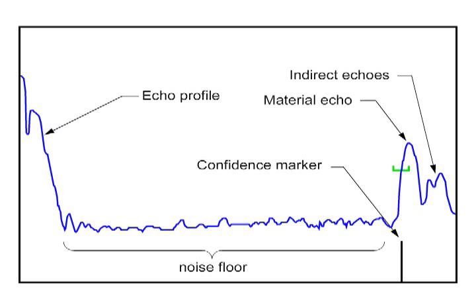The green trough shaped line is the echo lock window. The width of the echo lock window represents the measurement tolerance. If on the next pulse, the true echo was located outside of the current echo lock window, this measurement would be rejected.